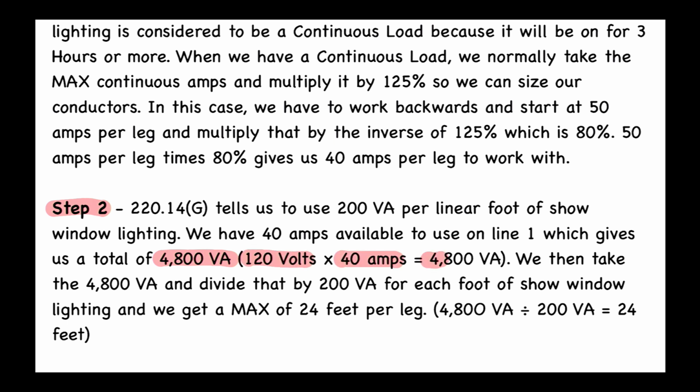We then take the 4,800 VA and divide that by 200 VA for each foot of show window lighting, and we get a max of 24 feet per leg.